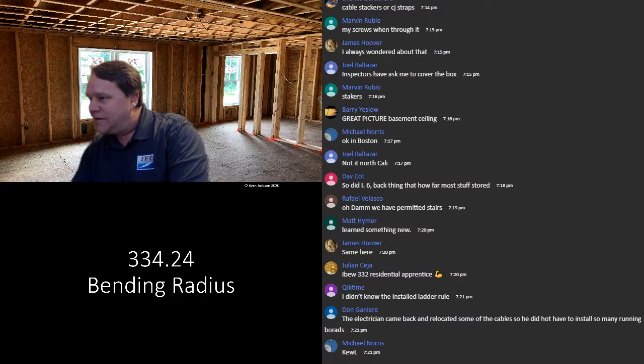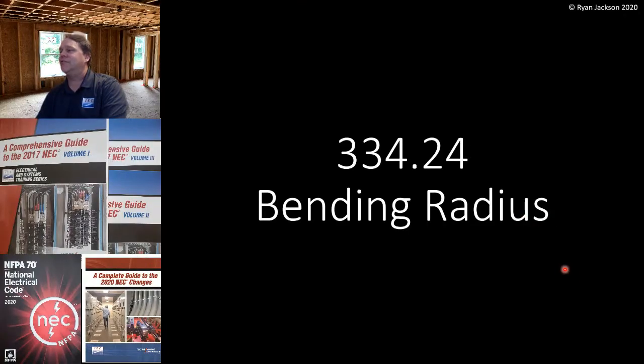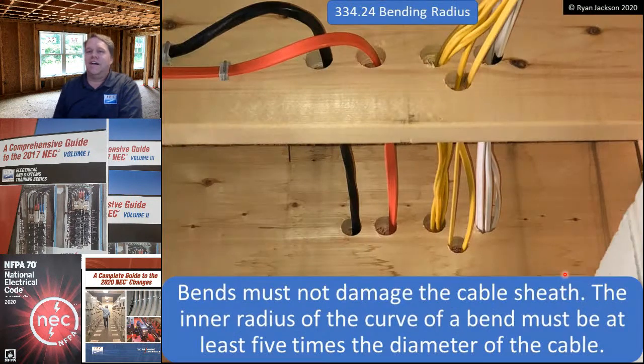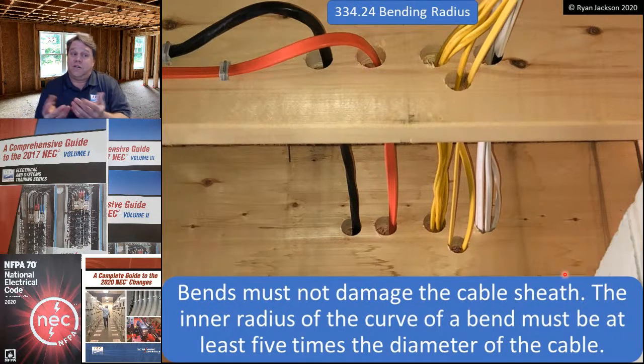334.24. Bending radius. Bending radii. I like to say radii. I don't know, it's just a word I enjoy saying. Bends must not damage the cable sheath. First and foremost, if you bend it and you damage the cable sheath, that's a violation. Also, the inner radius of the curve of a bend must be at least 5 times the diameter of the cable.